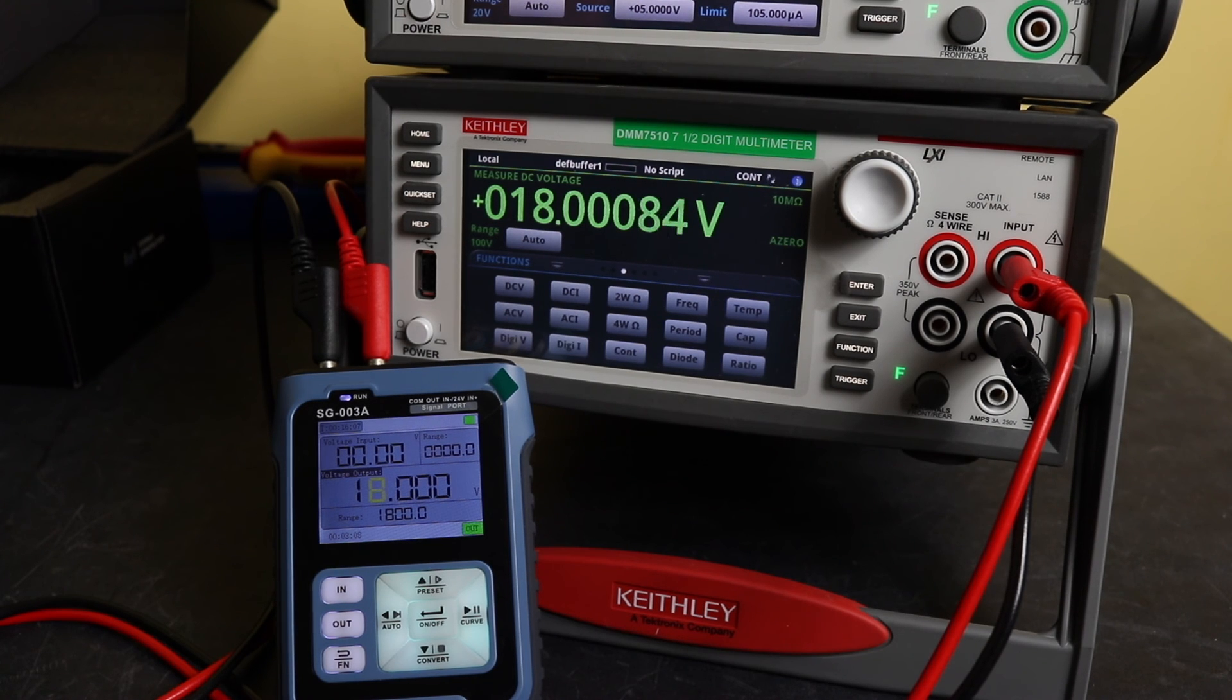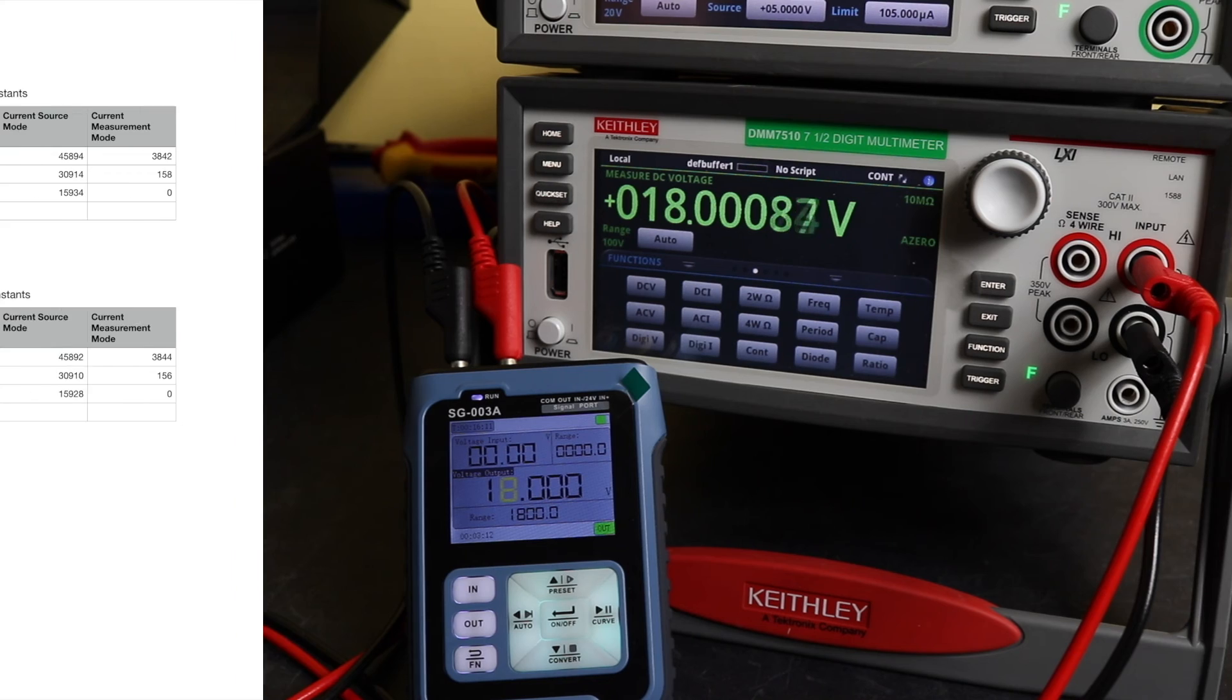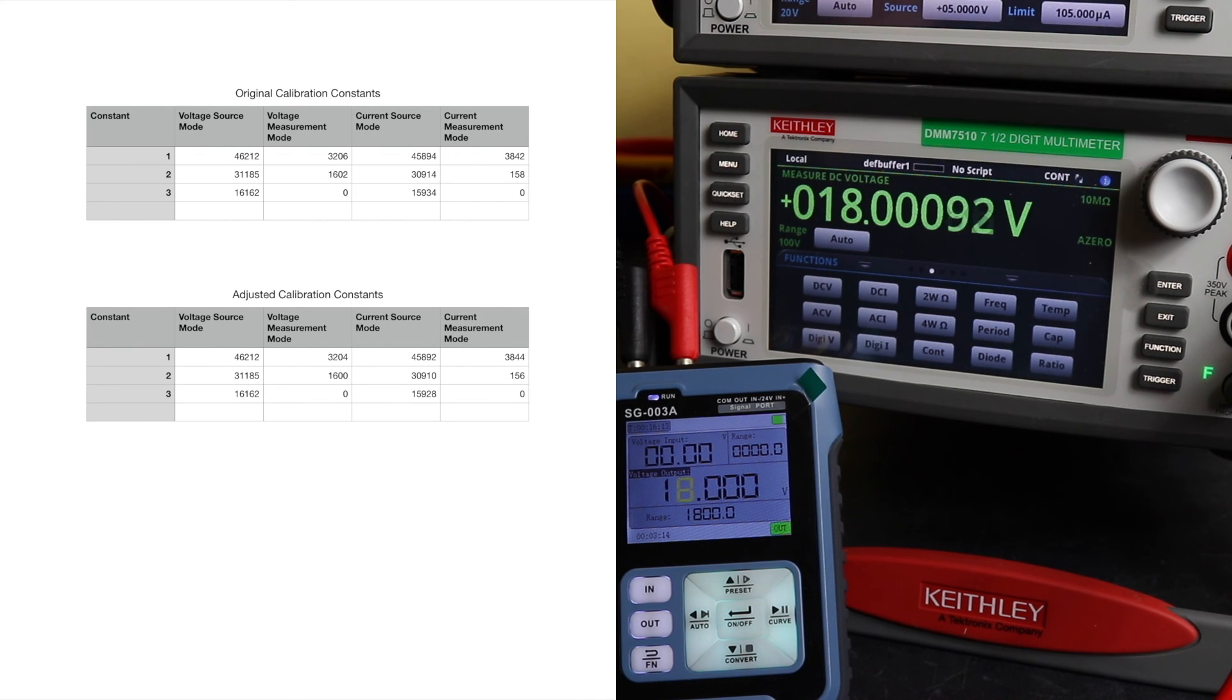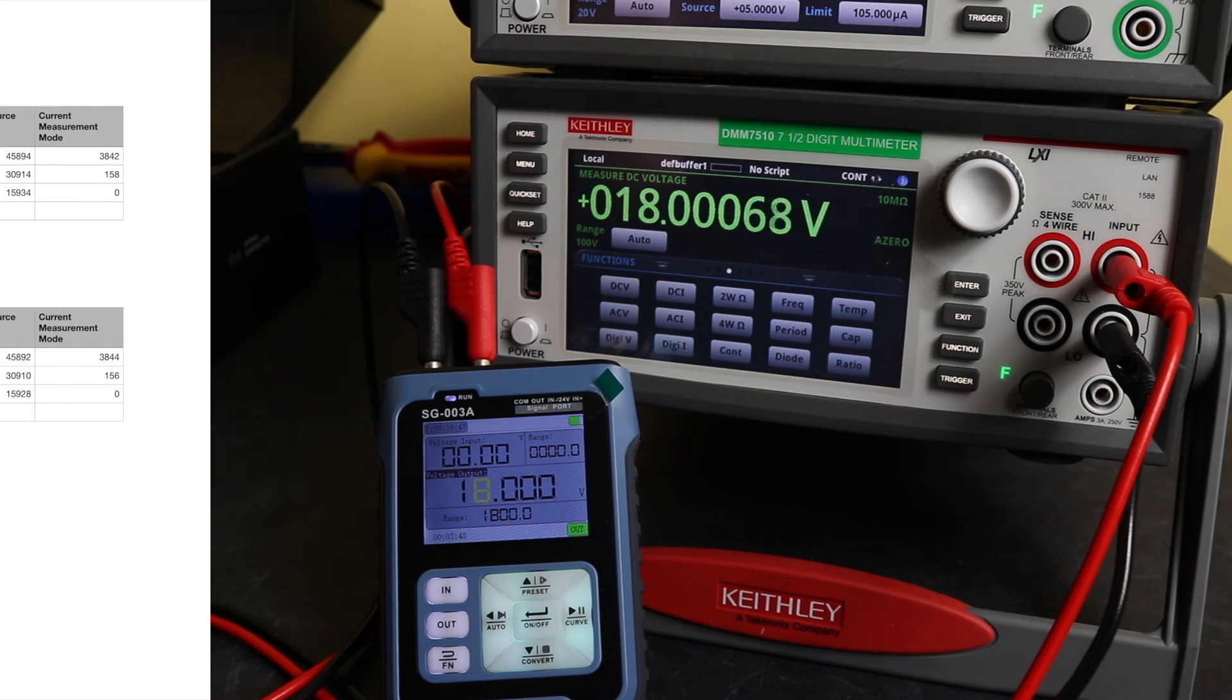Put this final table up, you see here we've got our original calibration constants that I had and then the adjusted ones, the ones that I adjusted them to to get those readings that you've seen on the other tables. So it was the voltage source, yeah, the voltage source I never touched. I've left them as they were. It's just voltage measurement, current measurement, and current source I tweaked, not far away from them, but just enough to make a bit of a difference.